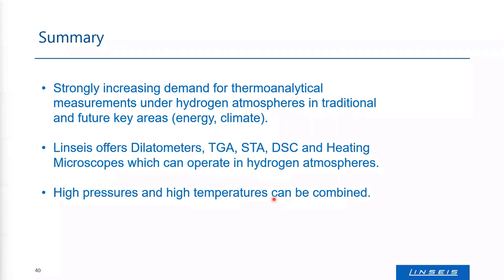We offer not only thermal analytical instruments to vary temperature, but also simultaneously the pressure. We can apply high pressures up to 150 bar, but also low pressures or vacuum down to 10⁻⁵ millibar. At the same time, we can vary pressure and temperature — also under hydrogen if requested.